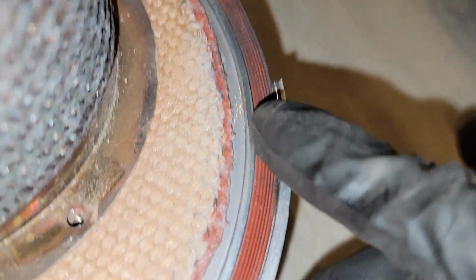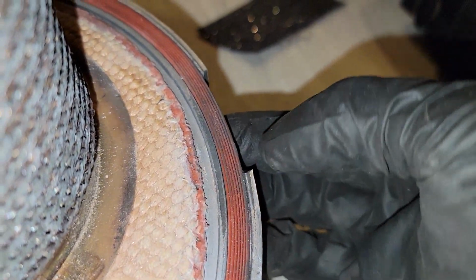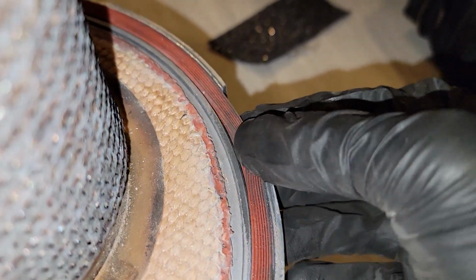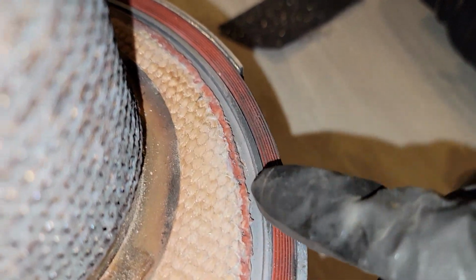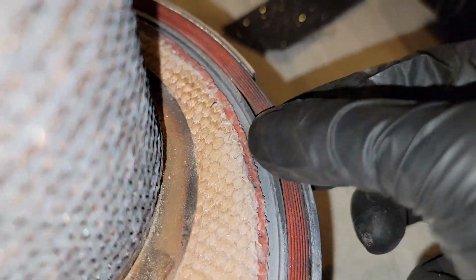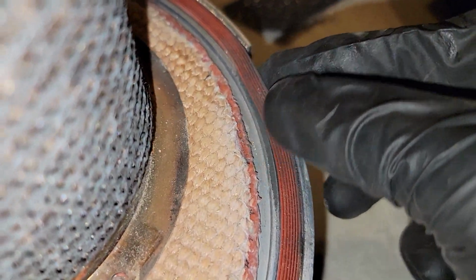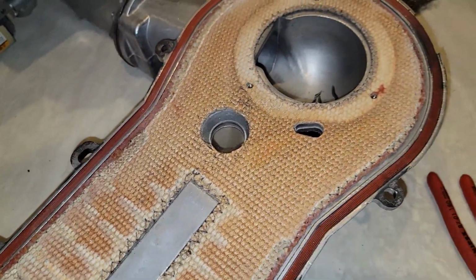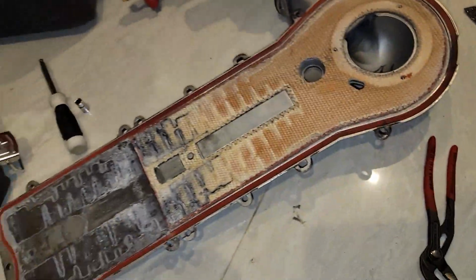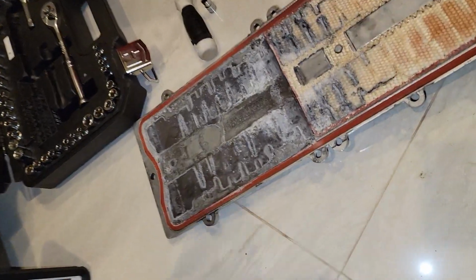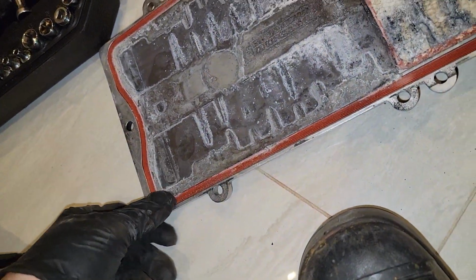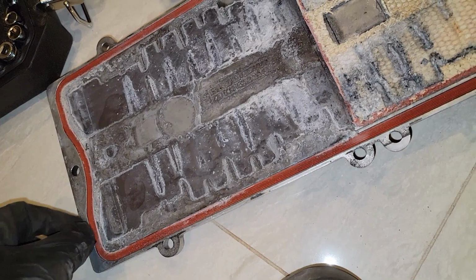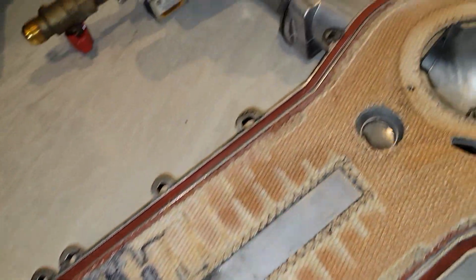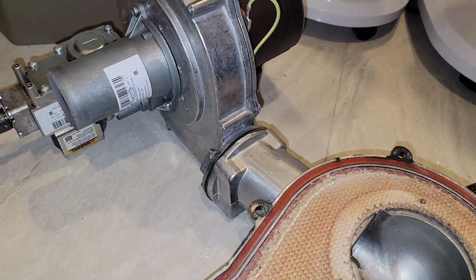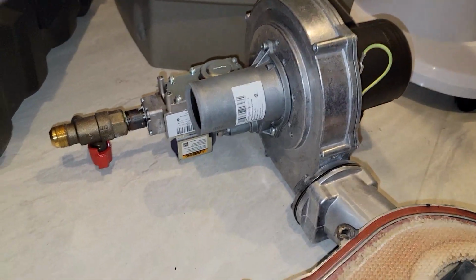Looks like combustion gases had been coming out there. My guess is that was already cracked, and when somebody put it back on, they couldn't hold it on tight enough, so combustion gases continued to come out. But I'm going to be replacing the gasket and everything on this still, even though a new part will be coming in. Then I'll replace the gaskets on the lower assembly as well.